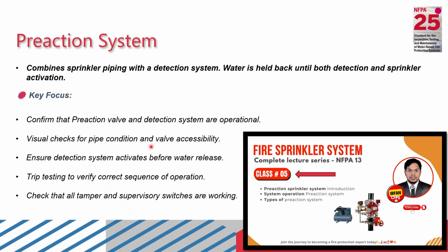Visual checks for pipe condition and valve accessibility. Ensure detection system activates before water release. Trip testing to verify correct sequence of operation. Check that all tamper and supervisory switches are working.